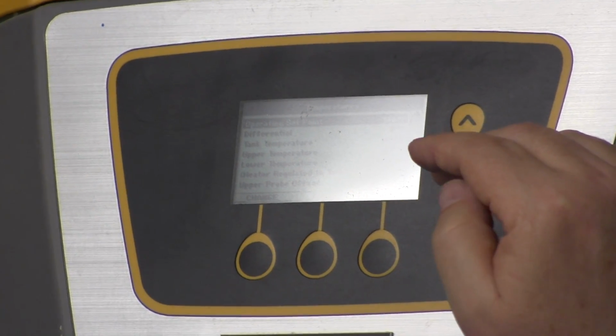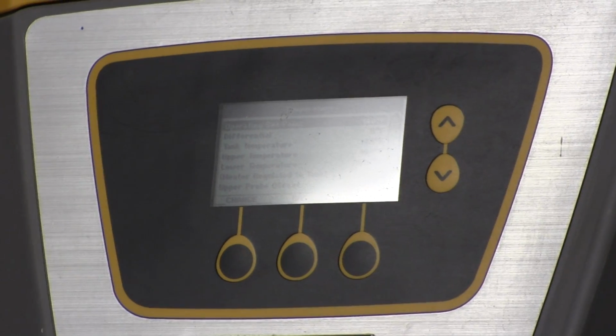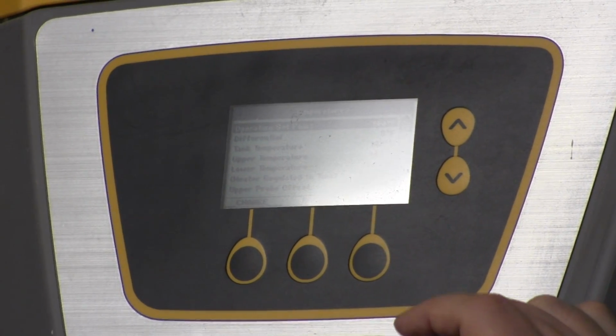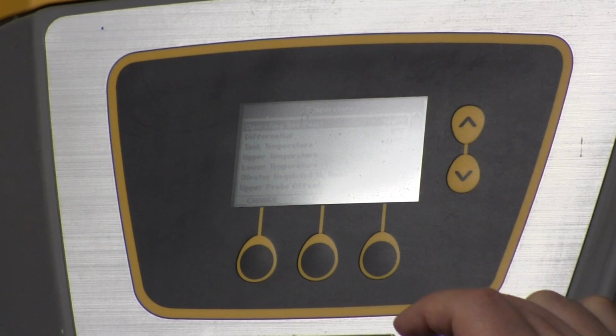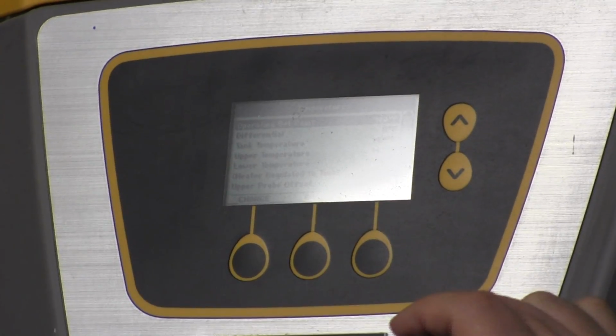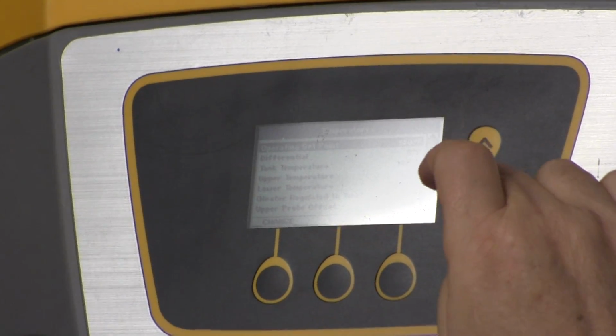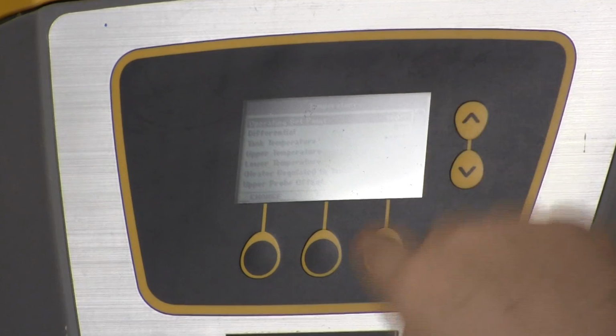So if you had, say, a 2-degree differential, these things heat up pretty fast. The heater would come on, go on, off. So an 8-degree is okay, but if for some reason it's not getting done, you can change that either way. And it'll tell you how it's computing that.